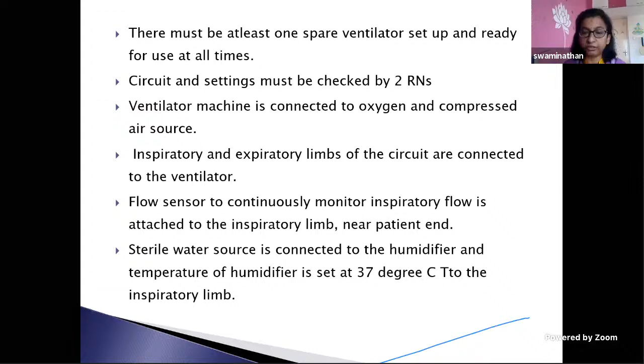Very important is that the inspiratory limb should be connected to the humidifier, and the humidifier connected to the endotracheal tube. That's very, very important. The thermal probe of the humidifier should also be connected. And the inspiratory and the expiratory limb, as I showed in the picture, are connected to the ventilator. If you have a flow sensor ventilator, it should also be connected so that your tidal volume can be monitored. And for the humidifier, please make sure there is adequate water level and the temperature is set.